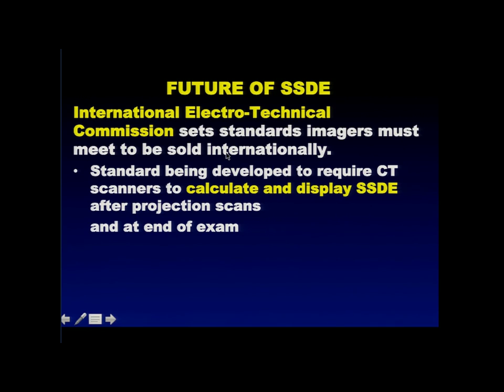And there's no CT manufacturer today that doesn't want to sell their equipment internationally. So we're currently on the IEC developing a standard that in the future is going to require the CT scanners to calculate and display the SSDE in addition to the CTDI vol.